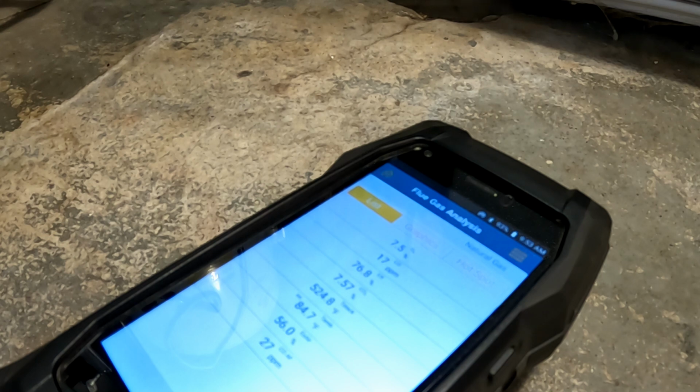So the concept of the low draft testing procedure is to identify and cure rising CO and lowering oxygen levels. In this case, we had lowering oxygen levels and high CO in the startup. So that'll come down. In the meantime, I'll get back to you.